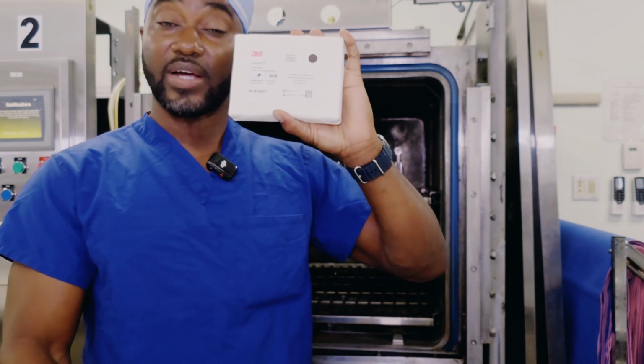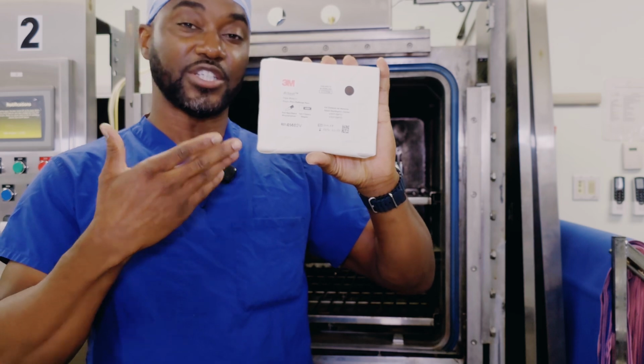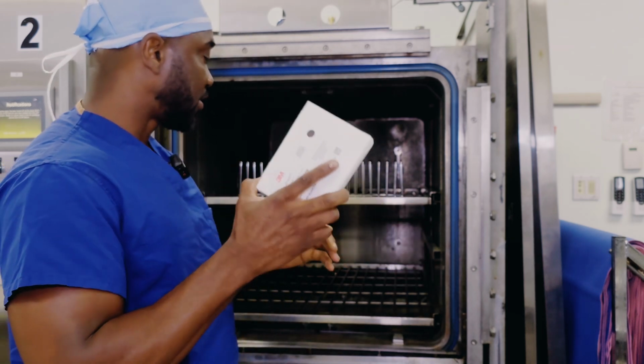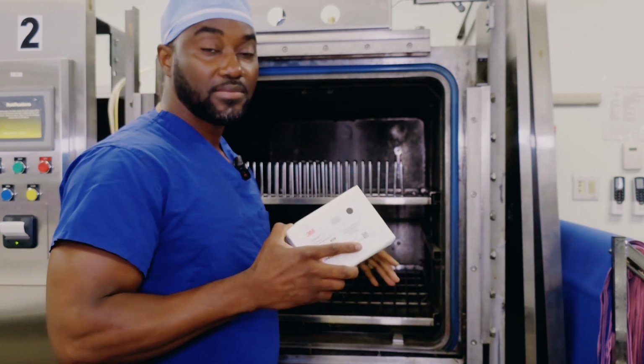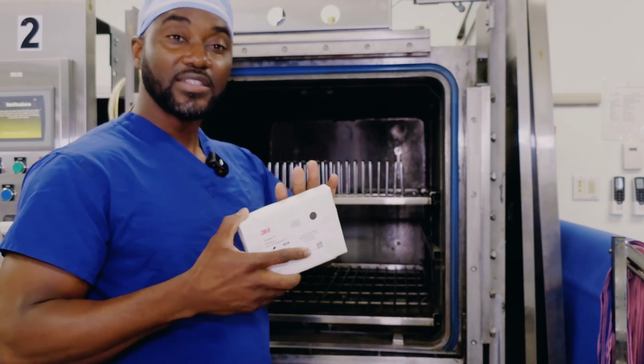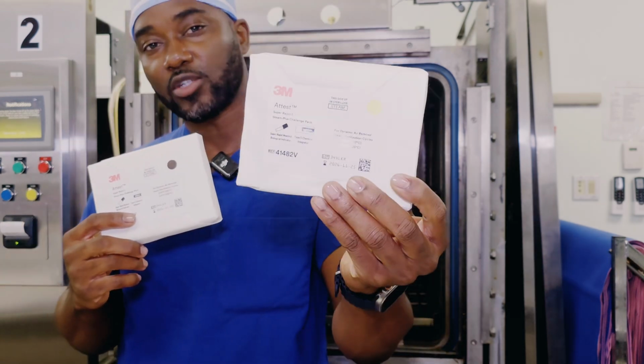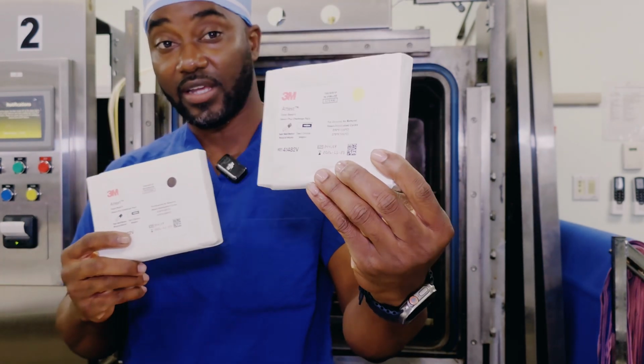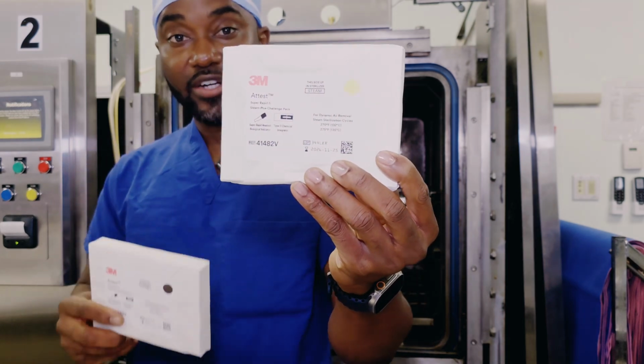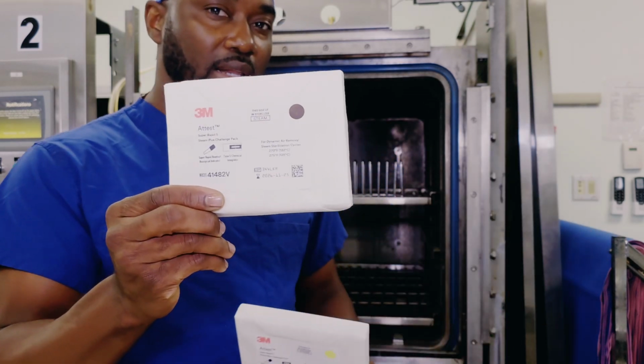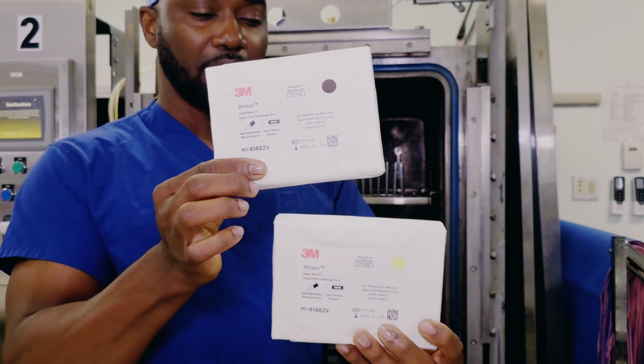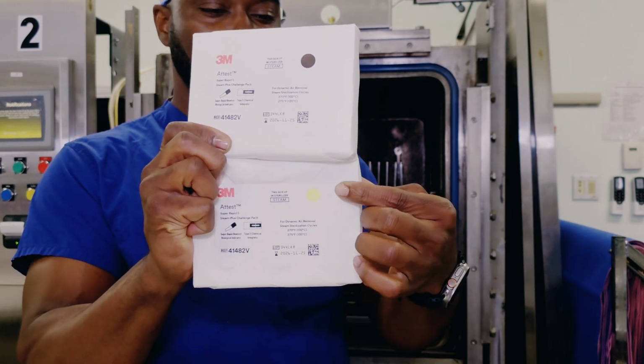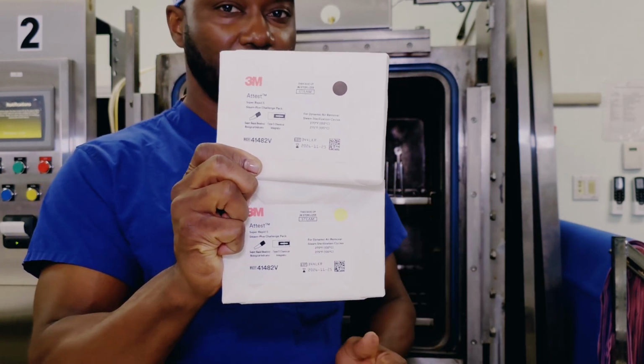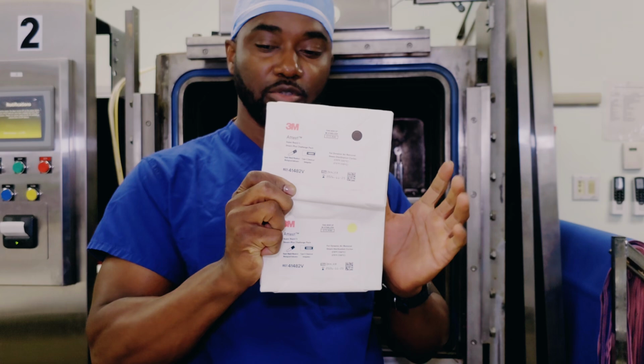This is a process challenge device. The definition is in the name. It challenges the sterilization process by testing the efficacy of steam. This is what it looks like before it gets into the autoclave. You notice that yellow indicator on the outside, and this is what it looks like when it has been exposed to steam. You notice that the yellow color has changed to what? Black up here, because this has been exposed to steam.